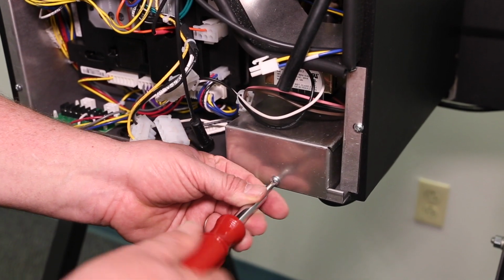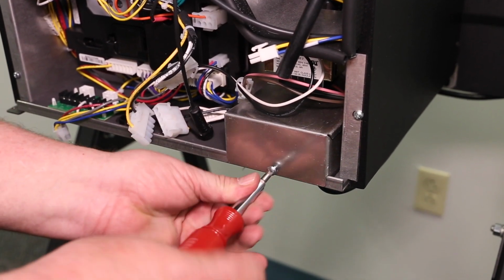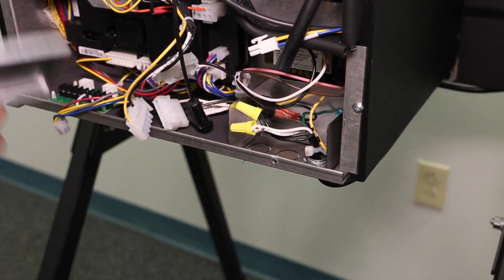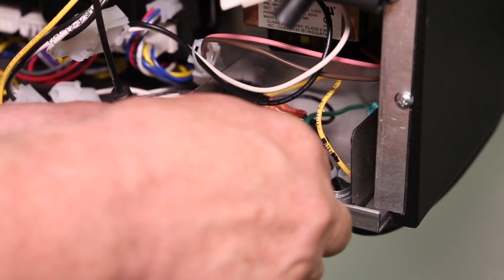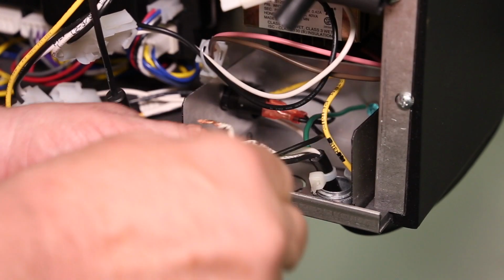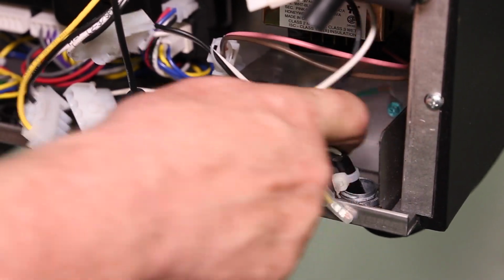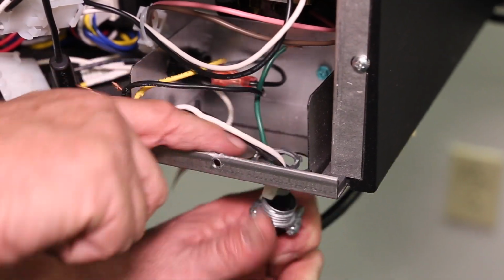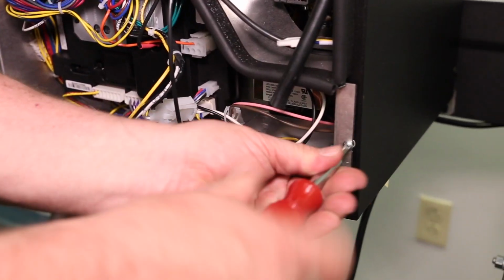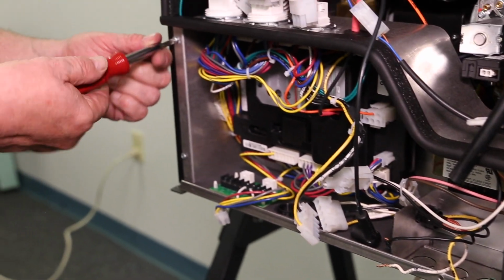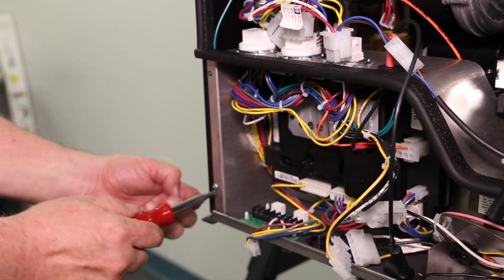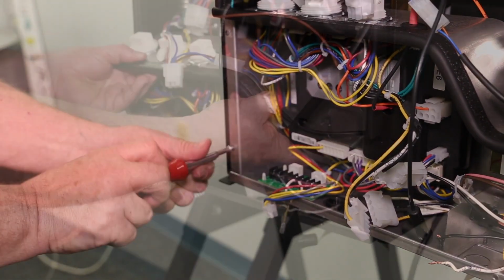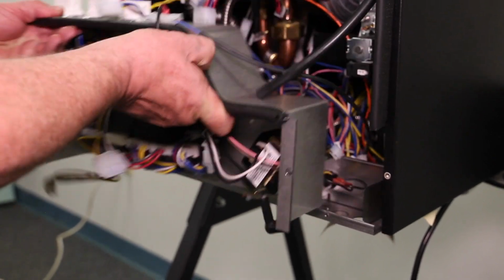Next, remove the junction box cover by removing 1 Phillips head screw. After removing the cover, disconnect the incoming line voltage wiring connections in the junction box. This includes loosening the green ground screw in order to disconnect the ground wire. Next, remove the control box from the boiler. This is done by removing the 3 Phillips head screws from the control box assembly. Then pull the control box out of the boiler chassis.